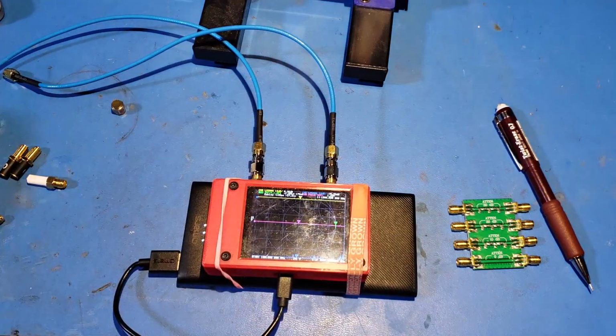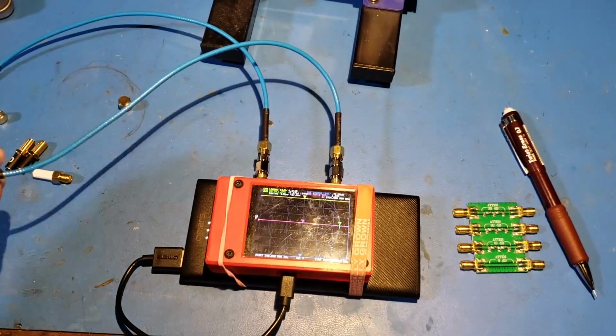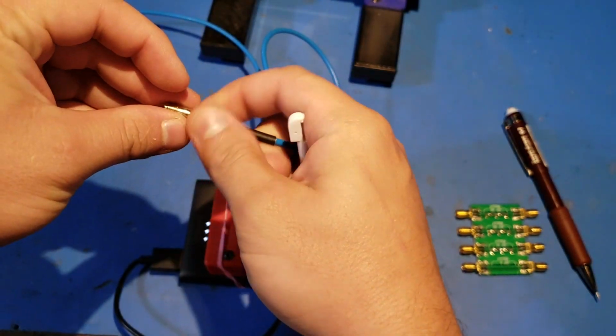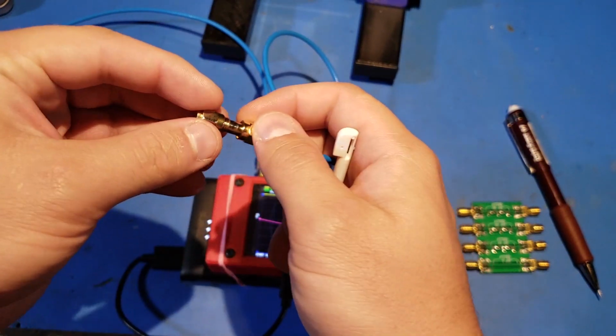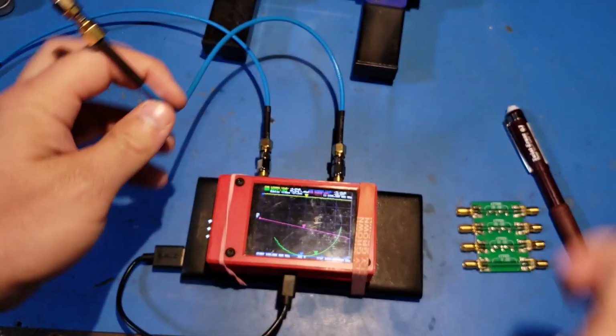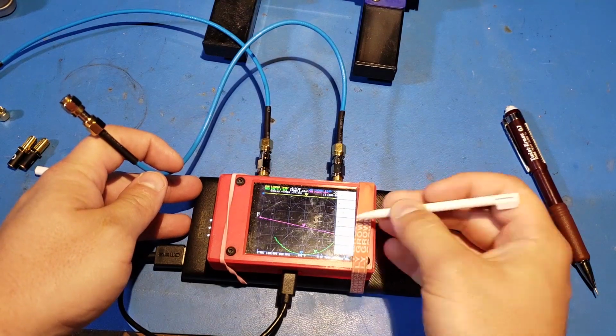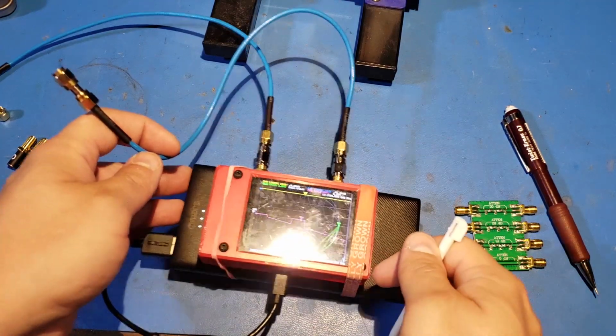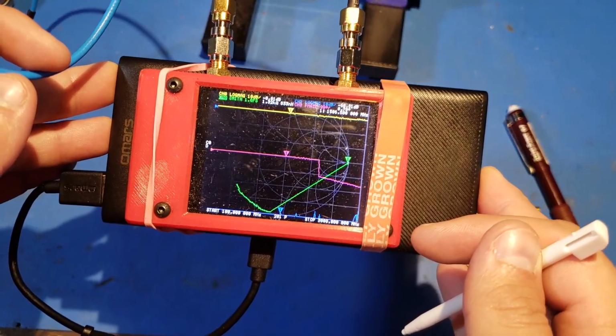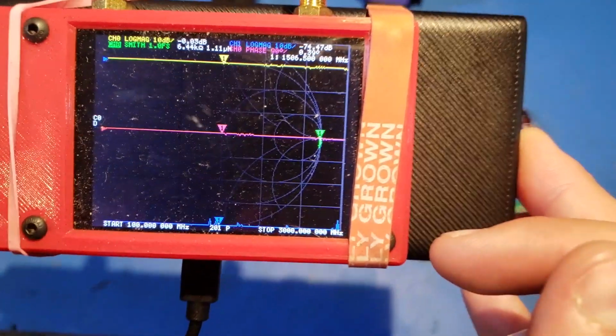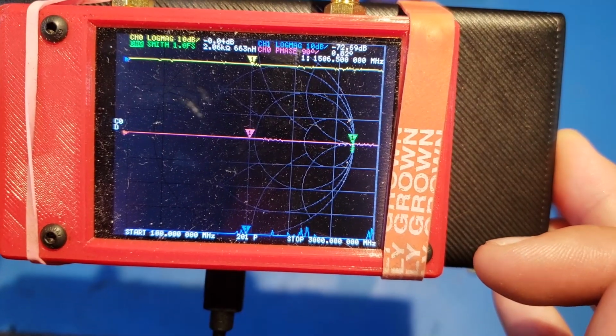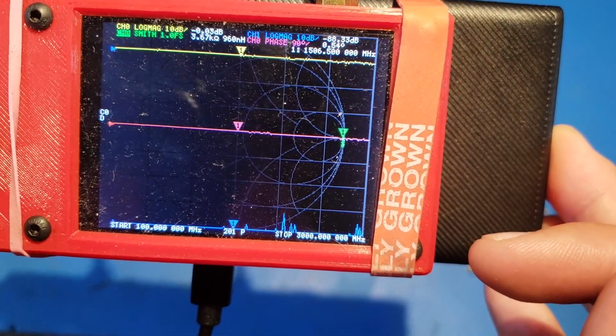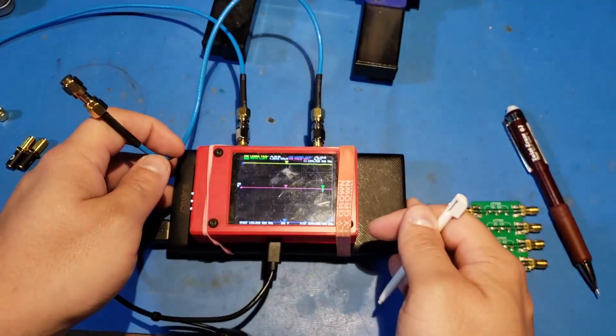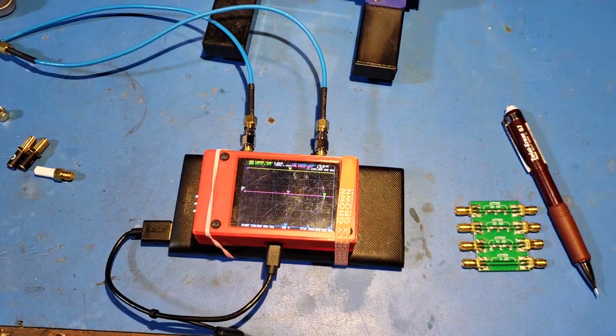Now, just as a point of comparison, because I didn't show in detail that it was indeed a positive value when we had the standard on the other calibration, I'll add this port back, and then I'll place the open circuit standard on it, and we'll look at that on calibration 1 real quick. So here, if we go back and we recall calibration 0, actually, not calibration 1, we can see that that's a dot on the far right of the Smith chart, and that value for impedance is like 6 kilo ohms, fluctuating between a couple kilo ohms actually, and it's positive. So I think losses were not accounted for in doing that port extension, and that's what leads it to having a negative value there.